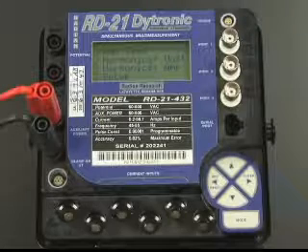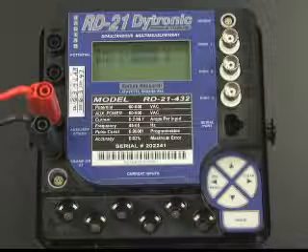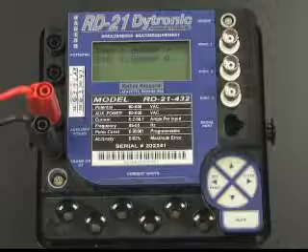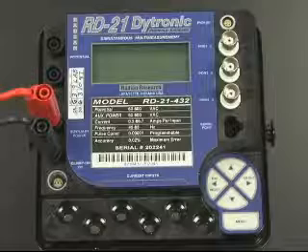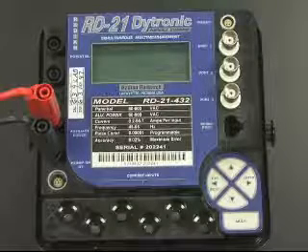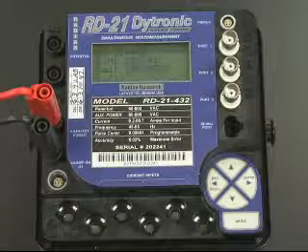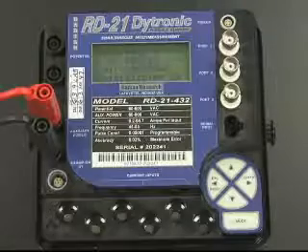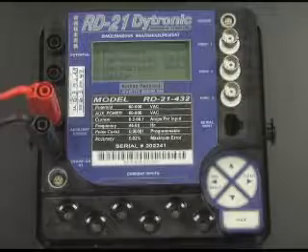The screens available on the standard are the main menu screen, instantaneous metrics screen, accumulating metrics screen, and the minimum and maximum measurement screen. When the unit is first powered, a screen containing relevant information such as a model number, serial number, and calibration number will appear for approximately 30 seconds. The standard will then begin to display the measurement functions it supports.